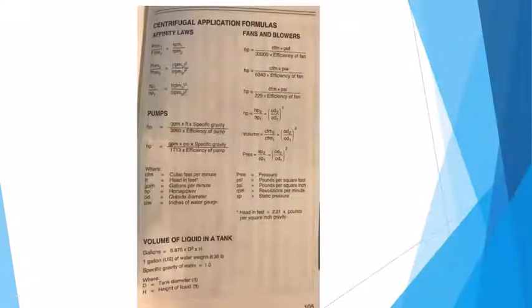The other area then is the actual horsepower and power draw. A lot of energy conservation has been considered about the affinity law, so that when you slow a motor down like 10%, the actual horsepower drops by the cube. And so, yes, it's fine, but you also have to look at the amount of flow, your total CFM, that you're providing for the item.